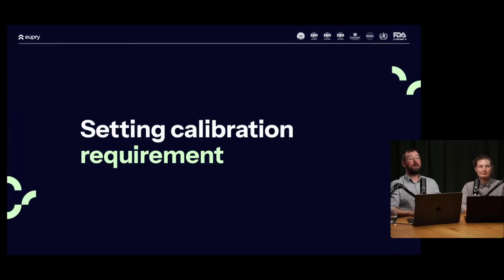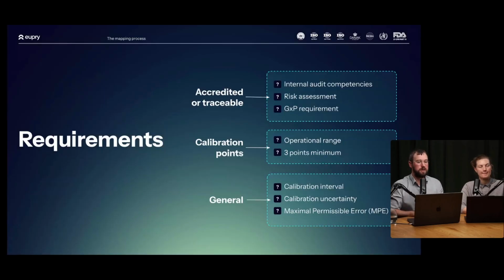So how do you set your calibration requirements? There are a lot of different requirements to set, but we've picked out the most important ones as we see it. So first of all, as we've just talked about, should you choose accredited or traceable calibration? I must mention as well, you can often in the same laboratory get both an accredited and a traceable calibration done. But first of all, you should consider, do you have the internal audit competencies? So can you actually go and assess a calibration laboratory with the technical expertise and the audit expertise to actually do this? If no, you might choose an accredited laboratory, and if yes, you can go away with a traceable laboratory.